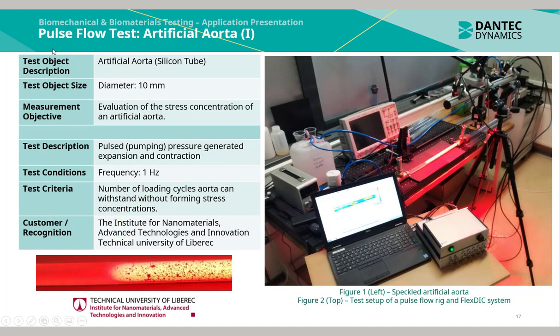This is a pulse flow test of an artificial aorta. The test object size has a diameter of approximately 10 mm. The measurement objective is to evaluate the stress concentration of the artificial aorta during a pulsed pumping pressure test, which effectively generates expansion and contraction of the aorta.